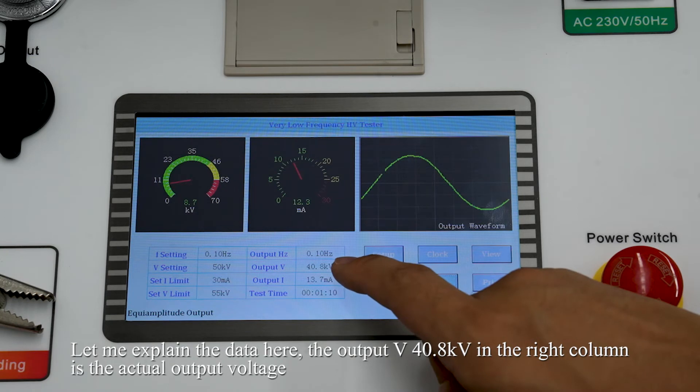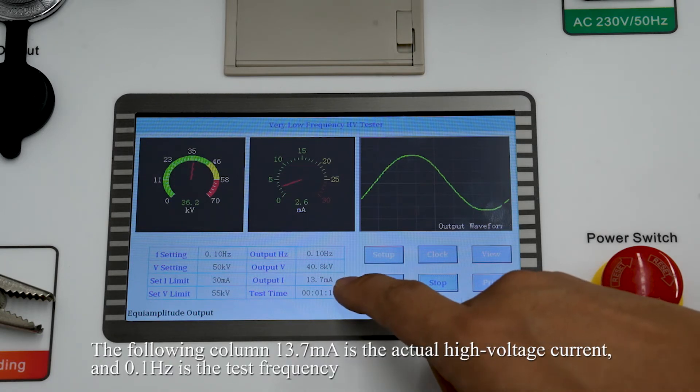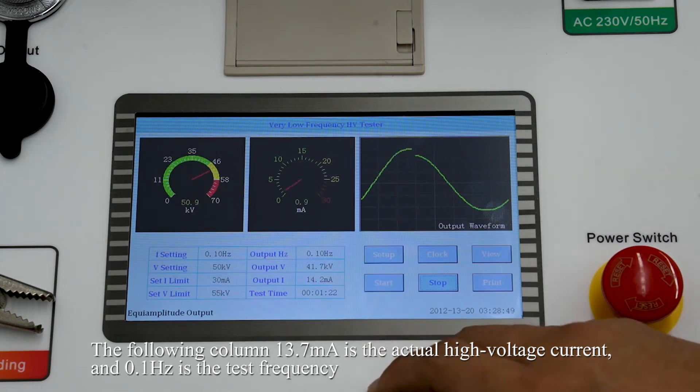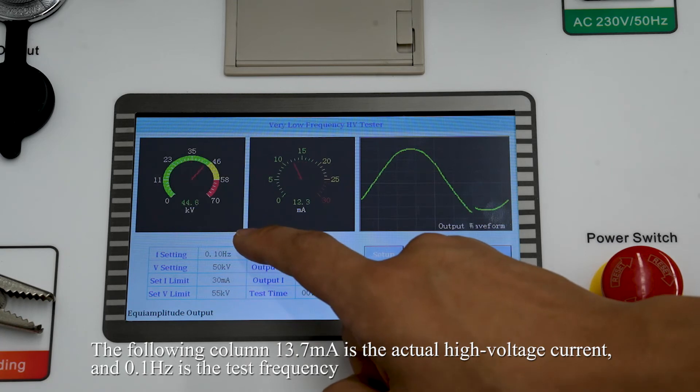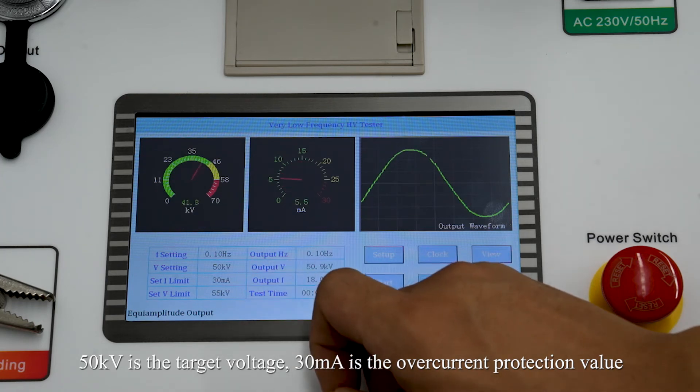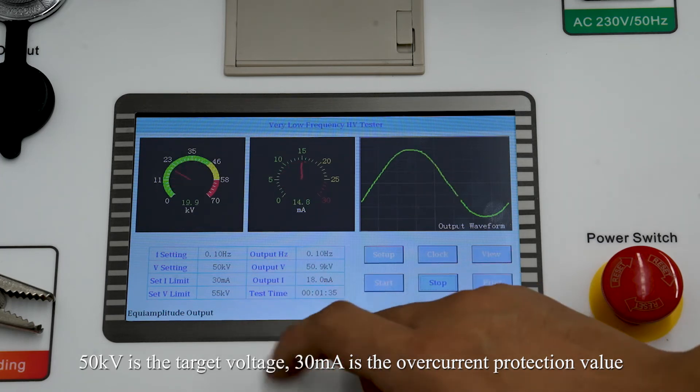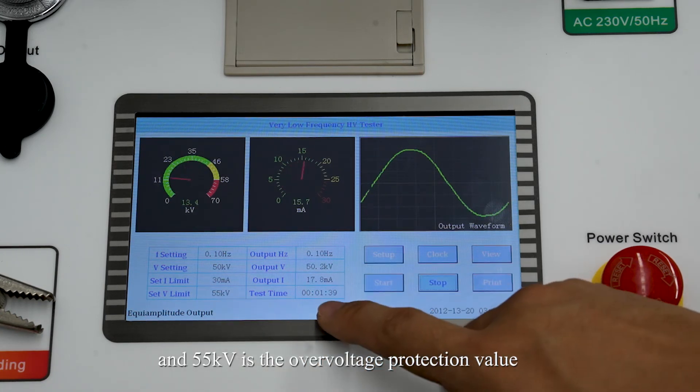Let's explain the data here. The output V 40.8 kV in the right column is the actual output voltage. The following column 13.7 mA is the actual high-voltage current. And 0.1 Hz is the test frequency. 50 kV is the target voltage. 30 mA is the over-current protection value. And 55 kV is the over-voltage protection value.